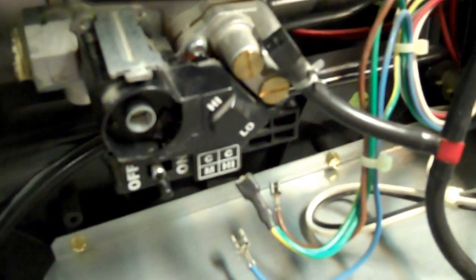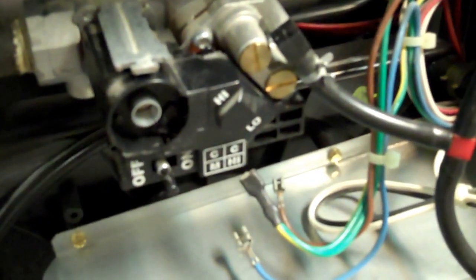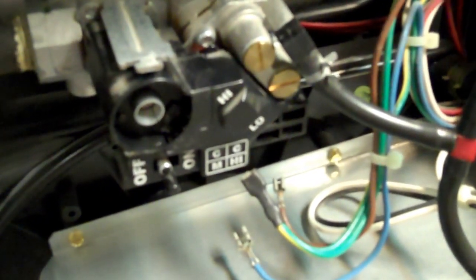So I've got the cover off, the plastic cover off. That's why it looks a little different maybe than yours. Anyway, the problem is the valve. So instead of getting the whole valve replaced, which is a lot of money apparently, I decided to look into it a little bit more. So what I did is I took the metal plate off. So I took that off, took the plastic cover off, and then you'll see two solenoids. This solenoid here is the big one. That's actually the one that opens the gas valve here and lets the gas go through. Well, what was wrong is this solenoid was open.